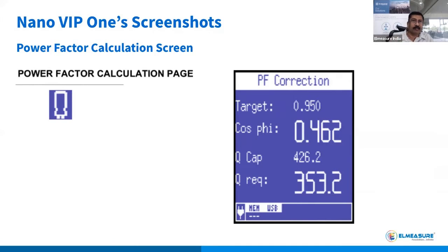It may be due to various reasons, but this product has a feature where you can set the power factor target, say 0.95 as an example. At that moment, when you try to set it, it will show what the actual cos phi present there is, which may be 0.4, 0.5, or 0.6, whatever it may be.